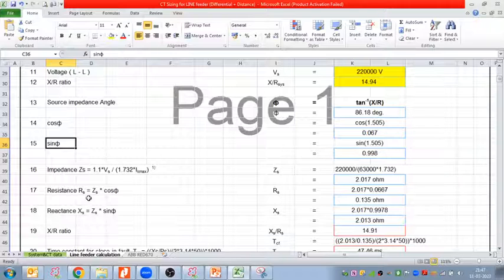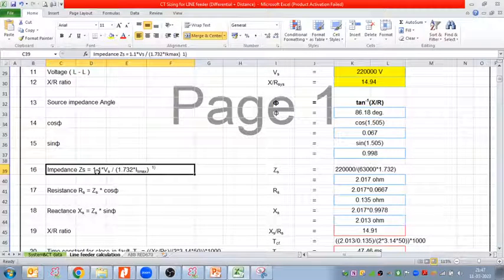Now we need to calculate the impedance Z, and based on that we will get the resistance R and reactance X. For impedance Z we follow this formula. See, the 1.1 is my margin, so forget about 1.1. Impedance value will be Vs divided by root 3 into I SC. It is a 3-phase system, so we take root 3 here. Since we are calculating the source impedance, we use the short circuit current. We also did this in the solar power plant short circuit calculations, right? So the source impedance is voltage divided by root 3 into short circuit current. This is how we calculate the source impedance Z.